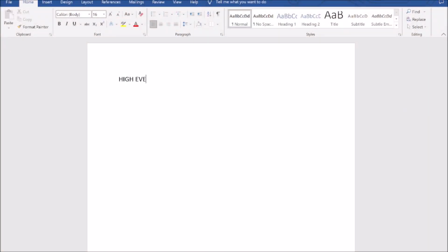All right, so our pressure switch high event was set to 78 PSI. So what does that mean? That means when we reach 78 PSI, our contacts will close, which will send power to the condensing unit. Okay, our differential was set to 38 PSI.